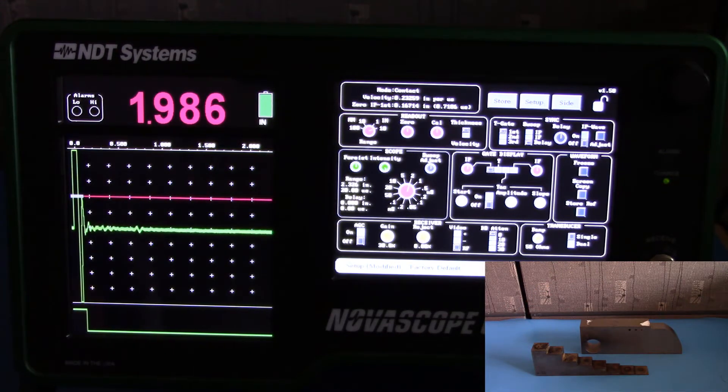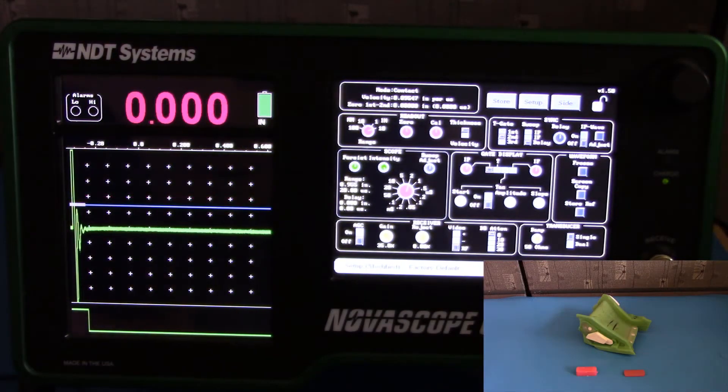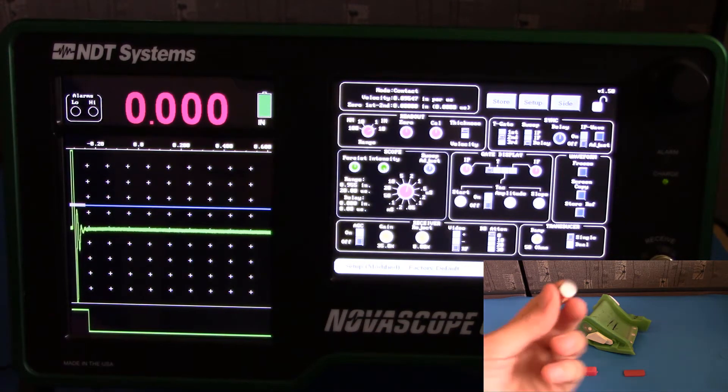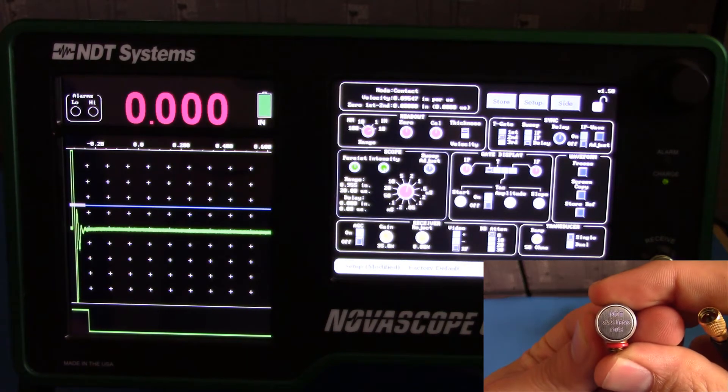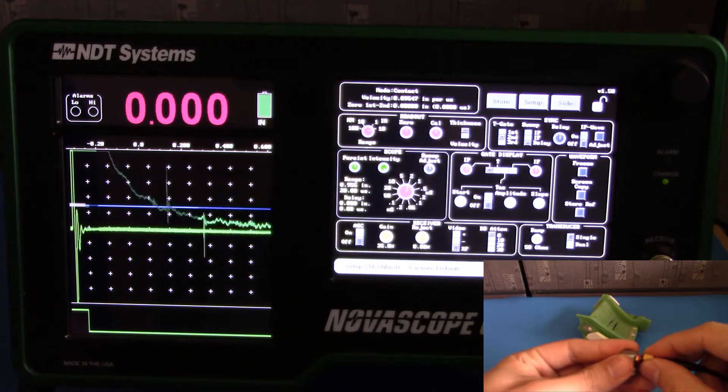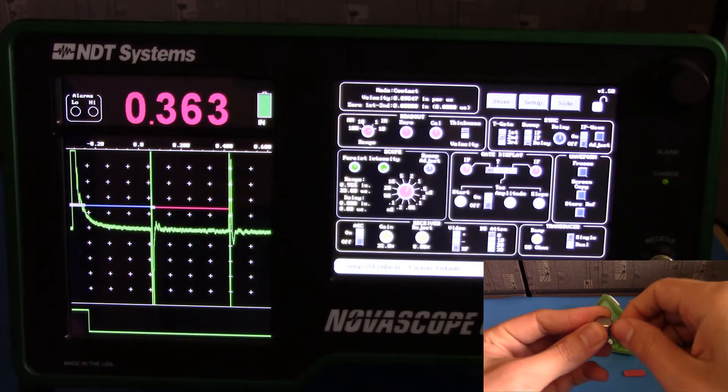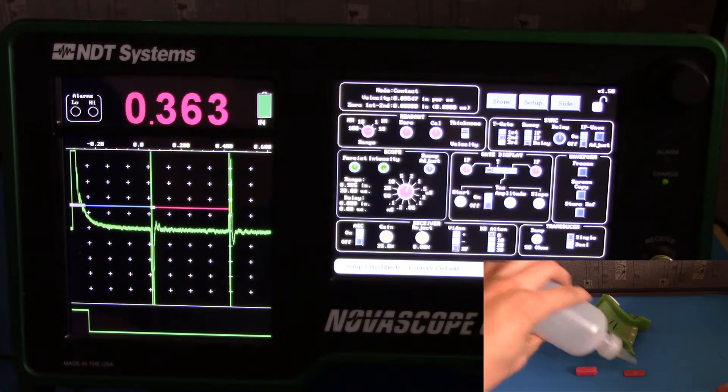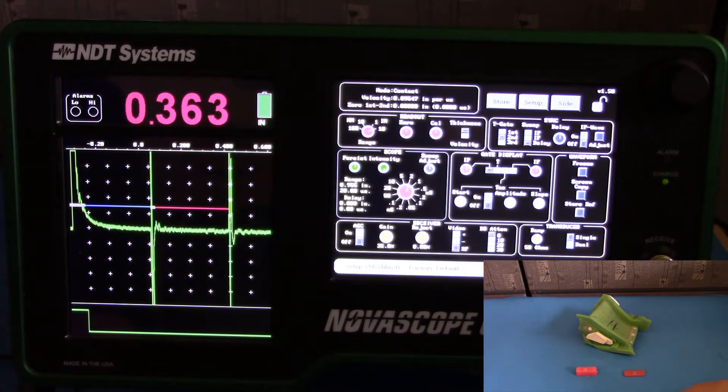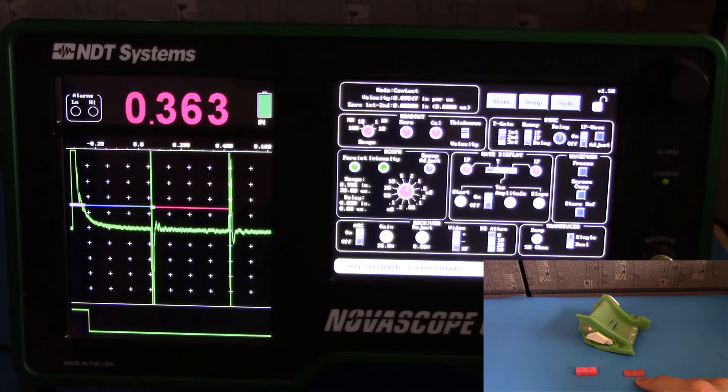Let's go ahead and look at delay probes. Setting up a delay line probe is similar to setting up a contact probe. In this case, we have an NDT Systems D11. We're going to connect it to the probe cable. We'll apply a couplant to our samples. In this case, we have a 0.1-inch wax shim and a 0.3-inch wax shim.